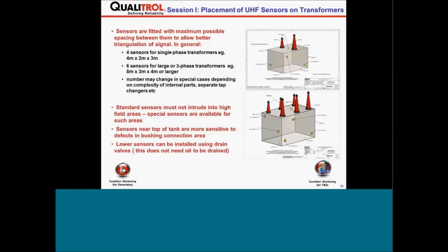Clearly these are basically our standard positions. We don't need them exactly here, but we're looking for them in these general areas. But clearly they would change depending on the shape of the tank and where the tap changer is, because we'd also monitor the tap changer at the same time.